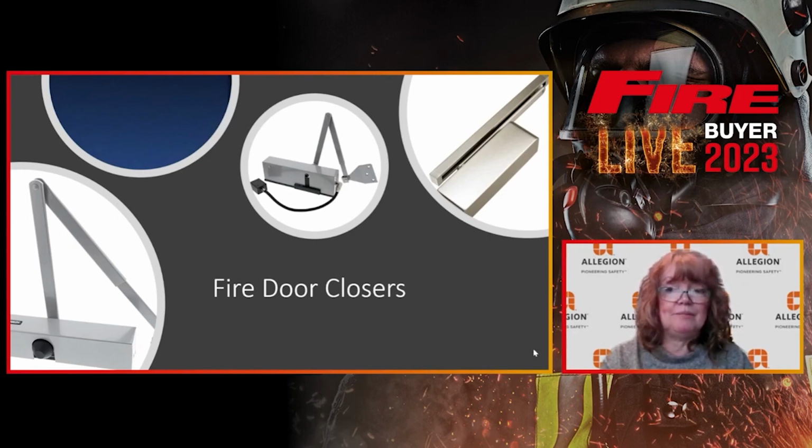You may consider, for instance, for high use areas such as hospitals or schools, the use of electromagnetic hold open devices that allow fire doors to shut once a fire alarm is activated. These units are linked to the building's fire detection system, which cuts power to the hold open unit, allowing the closer to shut the door firmly into the frame.